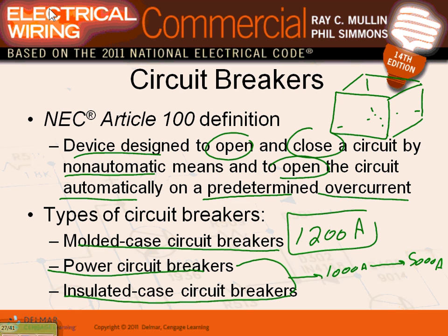This is what you're talking about, one foot by one foot by a foot. You draw out circuit breaker or bolted on circuit breaker. These are called power circuit breakers. Why? You can unplug them, put them on the bench, work on them, fix them, and then draw them into the switchgear and up and running.